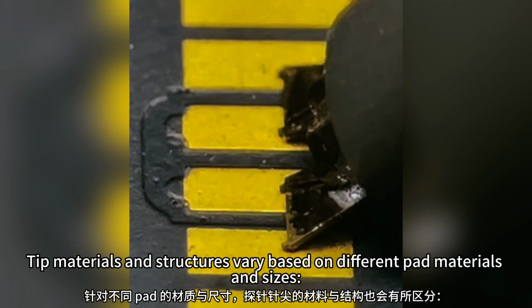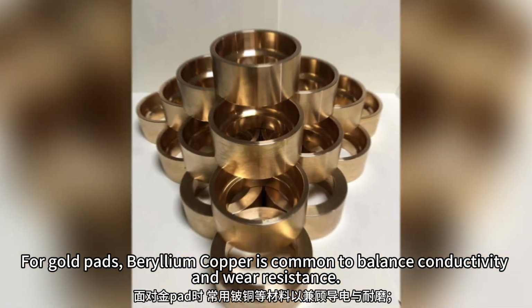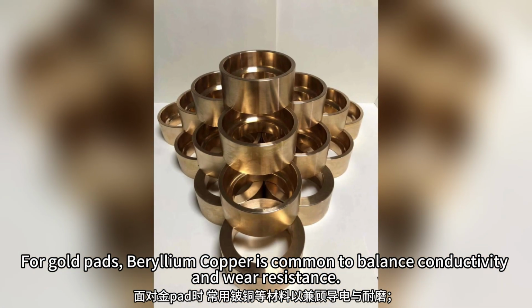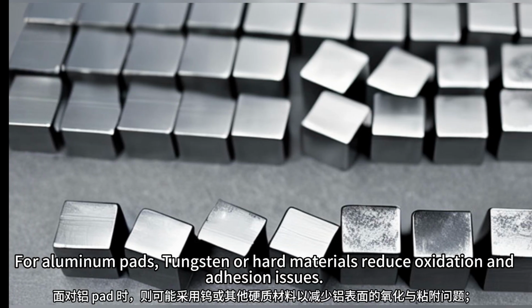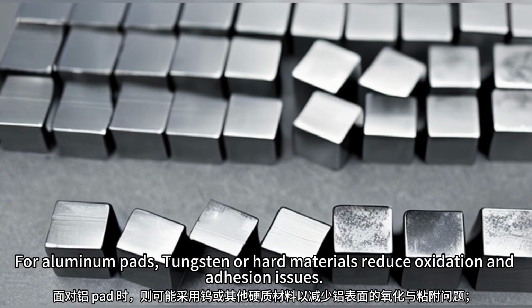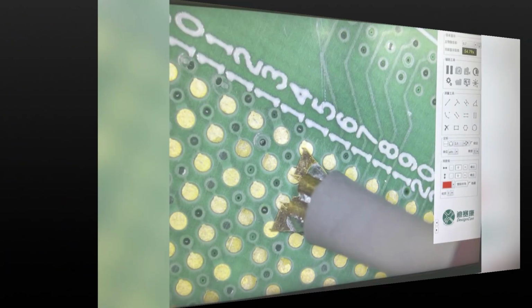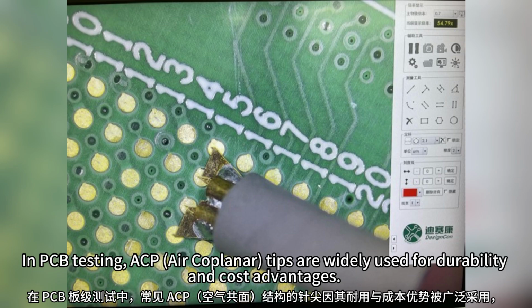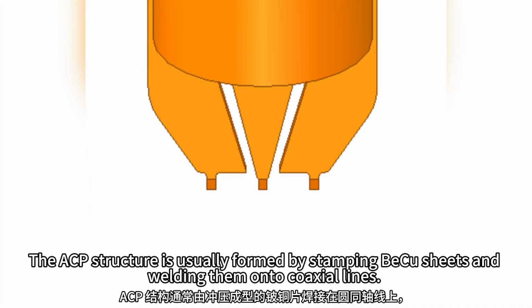Tip materials and structures vary based on different pad materials and sizes. For gold pads, beryllium copper is common to balance conductivity and wear resistance. For aluminum pads, tungsten or hard materials reduce oxidation and adhesion issues. In PCB testing, ACP air coplanar tips are widely used for durability and cost advantages. The ACP structure is usually formed by stamping BeCu sheets and welding them onto coaxial lines.